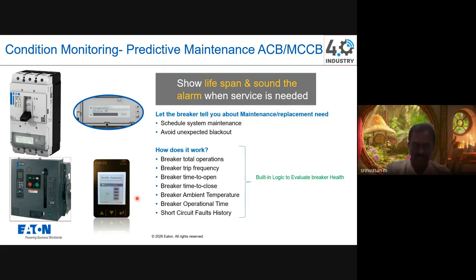We have two types of ACBs: the product which comes from Europe, and the ACB which comes from the Asia region. All the ACBs have this default feature, breaker health monitor. This feature is available with other manufacturers also, but the point to be noted is that you need to pay for it, and it has to be indicated in the project specification. Whereas in our Eaton, whether it's indicated in the project specification or not, we give this feature as a default in all our ACBs. And when it comes to MCCB, it becomes an optional feature.